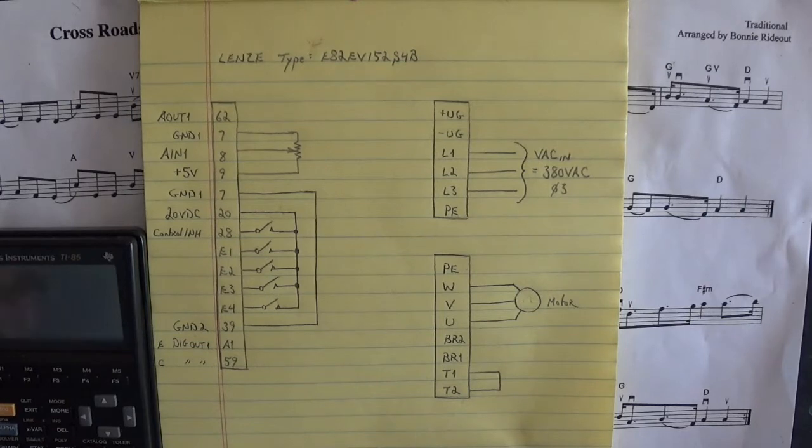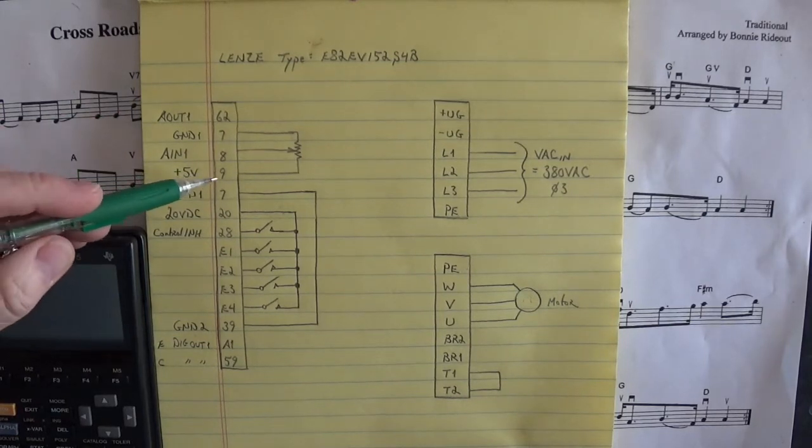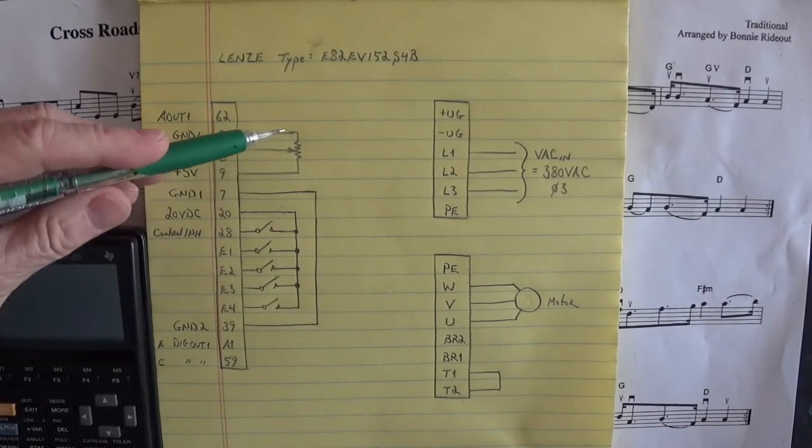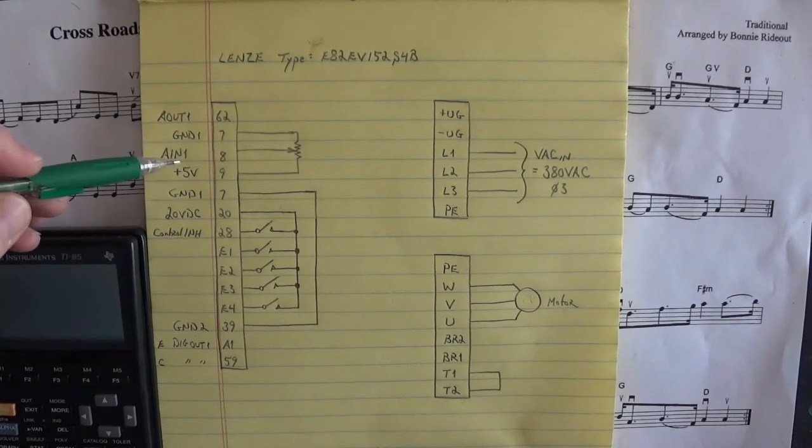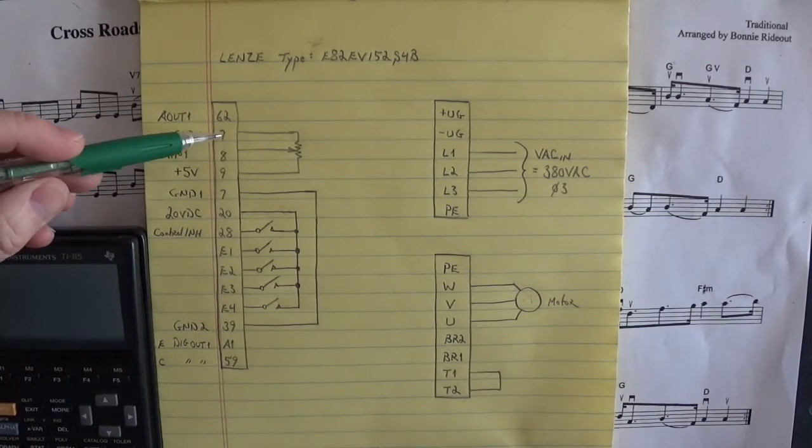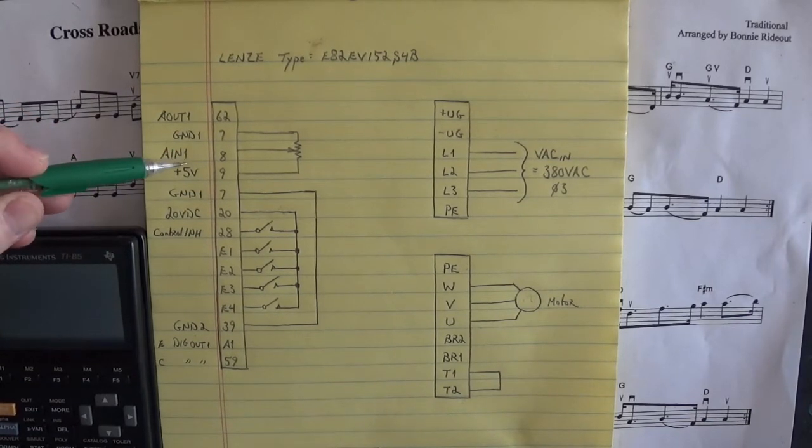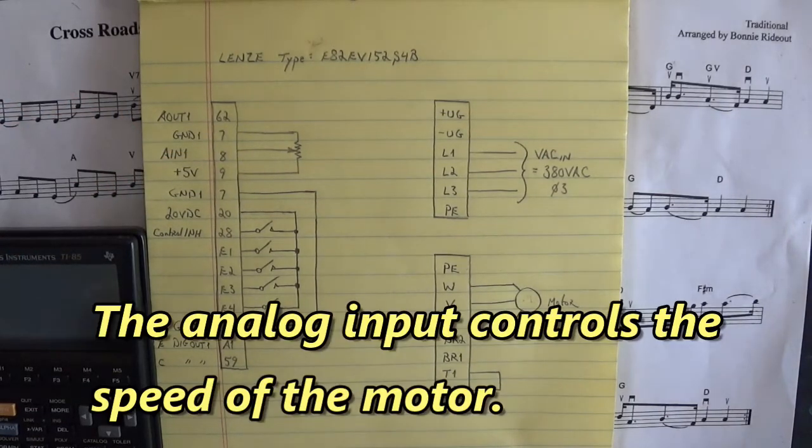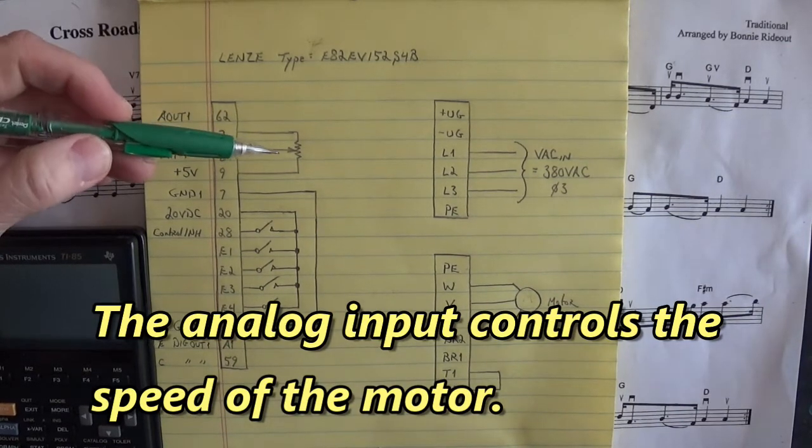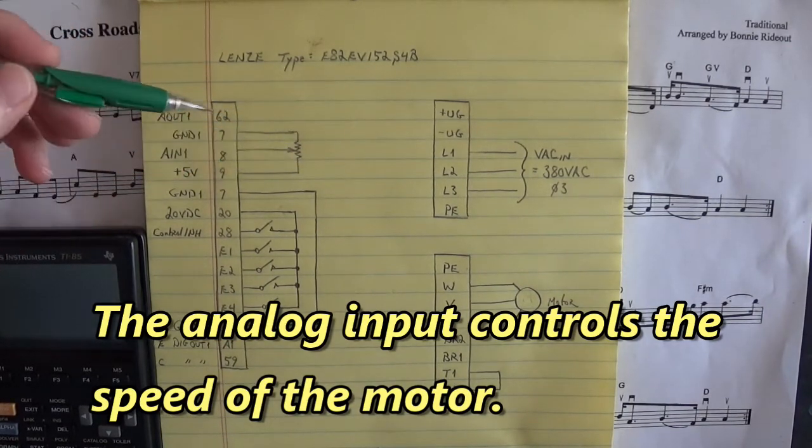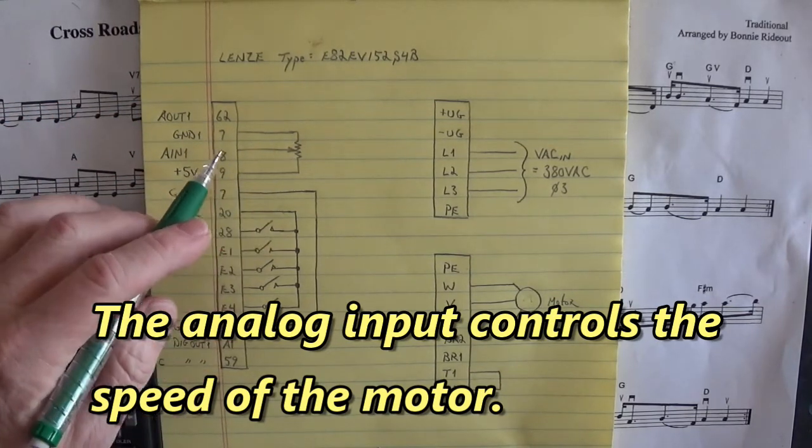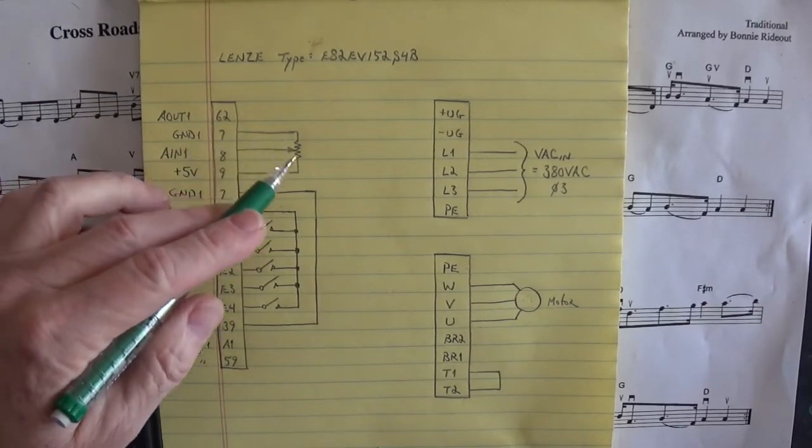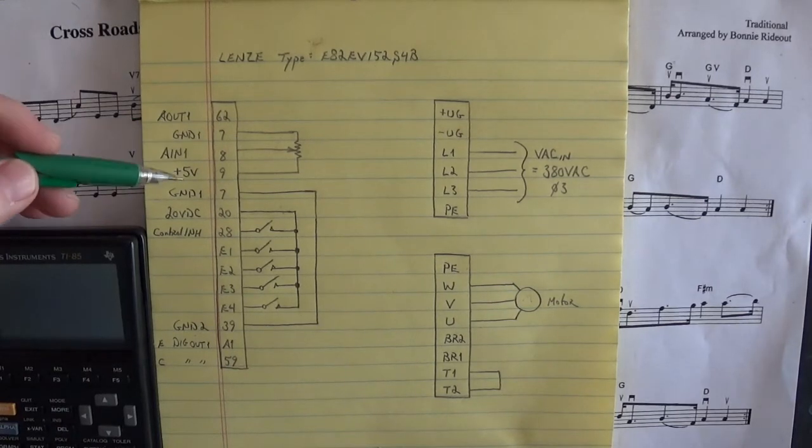On terminal 9 of that IO module you have 5 volts. This is for the external analog input. Ground 1 is on pin 7 and the analog input is on pin 8. So you put your 2 kilohm to 5 kilohm potentiometer out here, have the wiper go to pin 8, and the wings of the potentiometer go to pin 9 and pin 7.